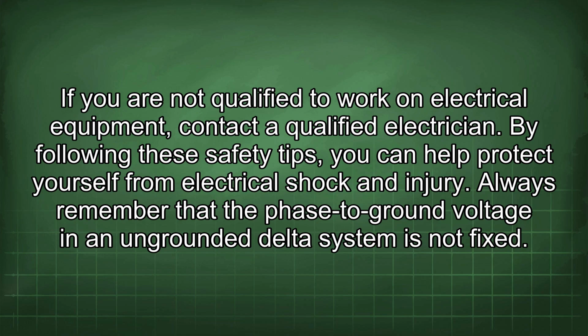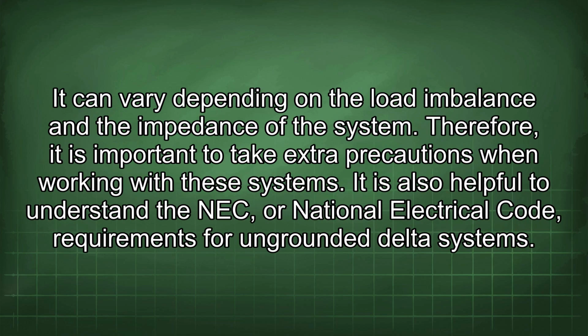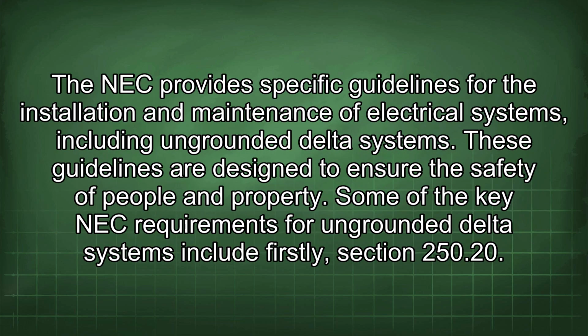Always remember that the phase to ground voltage in an ungrounded delta system is not fixed. It can vary depending on the load imbalance and the impedance of the system. Therefore, it is important to take extra precautions when working with these systems. It is also helpful to understand the NEC, or National Electrical Code, requirements for ungrounded delta systems. The NEC provides specific guidelines for the installation and maintenance of electrical systems, including ungrounded delta systems. These guidelines are designed to ensure the safety of people and property.